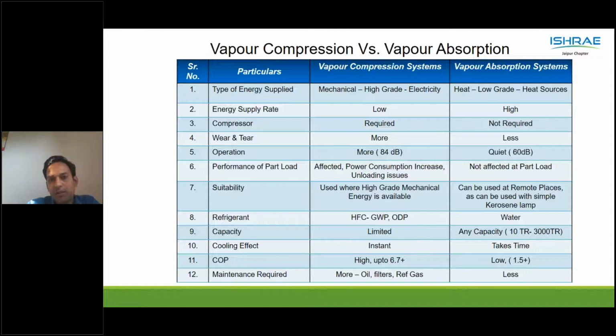The performance of the machines at part load is not affected in vapor absorption machines. For example, in vapor compression systems like screw chillers, there are stepped capacity controls, and screws cannot go below 30% capacity. These restrictions do not exist in vapor absorption machines. Also, in vapor compression systems, power consumption increases as we go to part loads, but that does not happen in vapor absorption systems, where the power consumption and energy requirement remain almost linear.